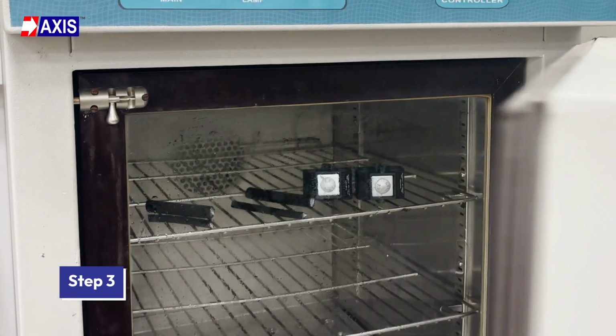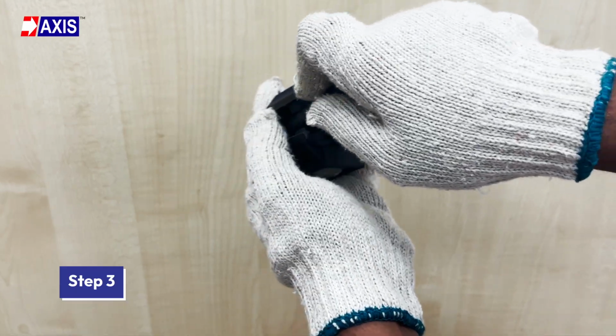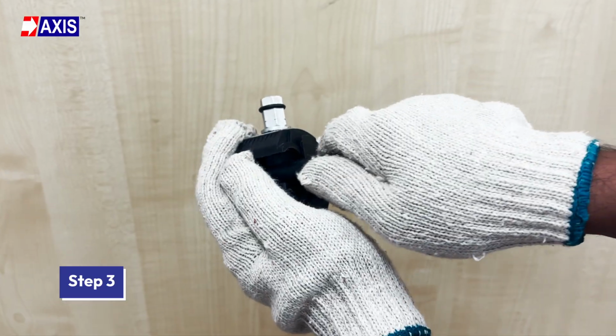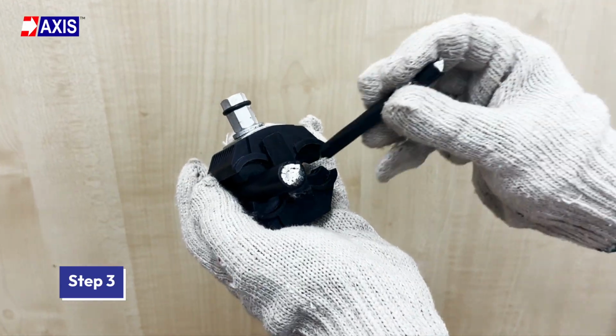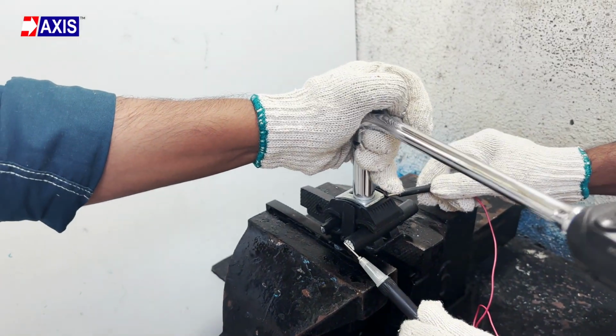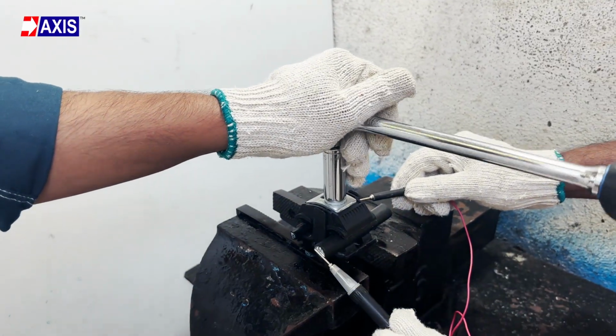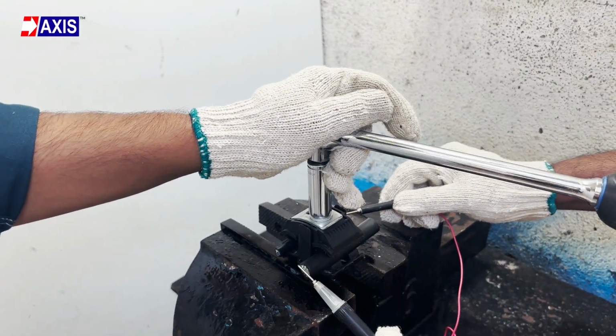Step 3. Assemble the IPC on the conductor while it is still at this temperature. Follow the manufacturer's installation instructions and use a torque meter to apply the recommended torque. 1 full turn in 8 seconds.